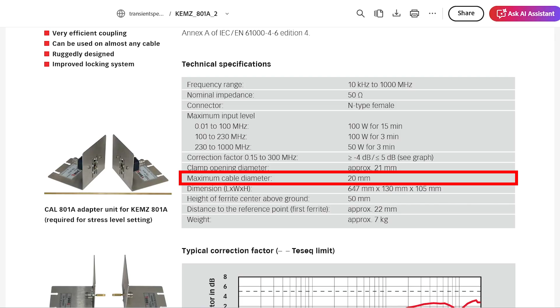The maximum cable diameter doesn't vary much between clamps, and they'll often be within a few millimeters of each other. If we take a look a little lower in the document, we can see the typical power requirements across the frequency range of operation to meet different test levels of IEC 61000-4-6, both with and without modulation. If we scroll a little lower, we can see we have a setup of the calibration or test level setting, which we'll go over here shortly.